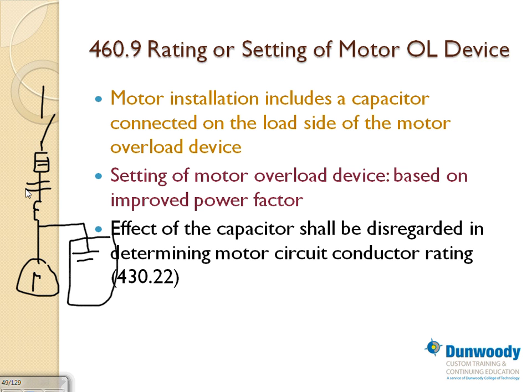So the current right here might be 10. By the time it reaches this point right here, it's actually 8, because I corrected the power factor and reduced the amps. So now the overload has to be sized based on 8, not the 10. That makes sense? Any comments, any questions? That's only if you put the capacitor back here. What if you put the capacitor right here? Then the overload is not going to be able to see the corrected power factor.